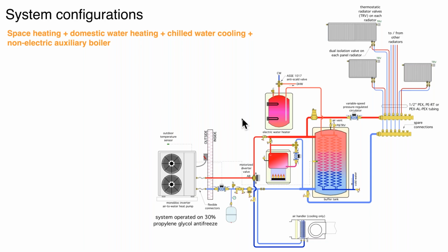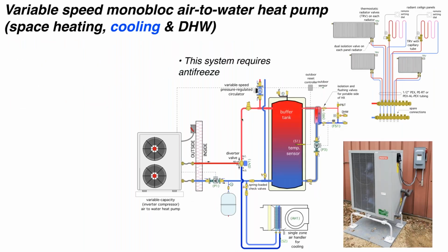So again, I know it's a webinar based on cooling, but I do want to mention, as you build these systems that are multi-mode or multi-load, be careful about protecting conventional boilers against sustained flue gas condensation. Here's another variation. The difference here is, instead of using a tank with internal coils, we're using, I'll call it a coilless tank, and we're using an external stainless steel heat exchanger as our domestic hot water, either preheater or perhaps even a full heater, depending on the temperature of this tank.